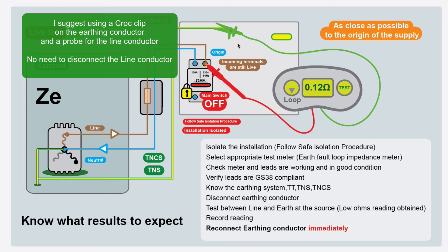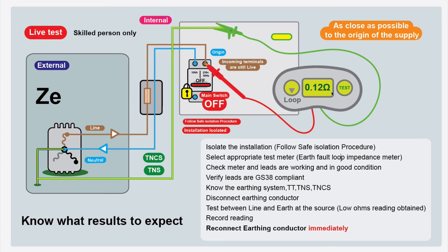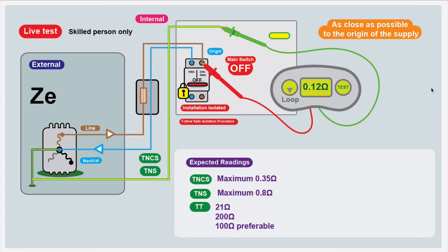Select an appropriate earth fault loop impedance meter set on the right setting. Check the meter is working, leads are in good condition and GS38 compliant. Know what kind of earthing system you've got and what results to expect. Then disconnect the earthing conductor, test between the line and the earth with your meter, record your reading, and — before doing anything else — immediately reconnect the earthing conductor. Don't walk away; as soon as you finish the test, reconnect the earthing conductor so the safety systems are back in place.